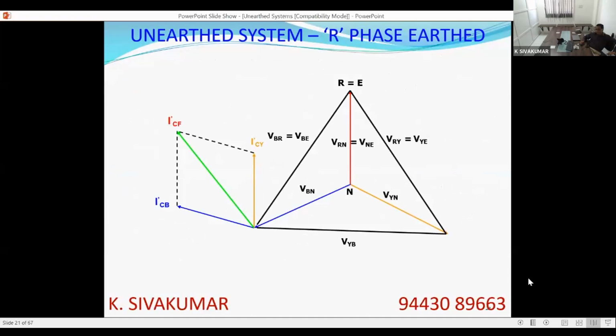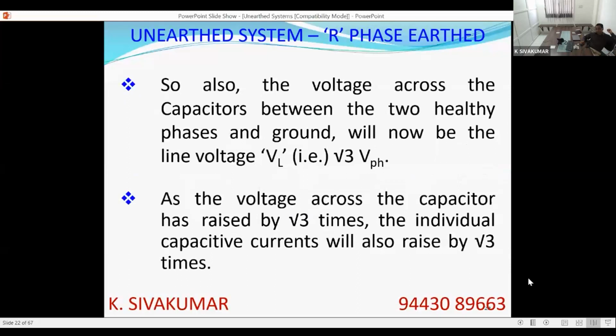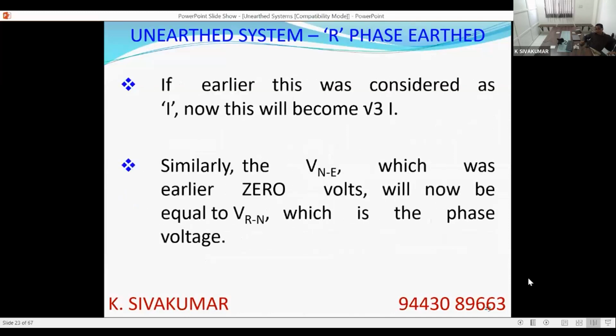That is, ICY will be leading VRY by 90 degrees, and ICB will be leading VBR by 90 degrees. The total net current flow during this fault, the capacitive discharge current, is the fault current. It is the vector sum of ICY and ICB. Since the voltage is increasing by √3 times, the current also will be increasing by √3 times. Earlier it was V phase by XC. Now it will be √3 V phase by XC. So the current will be no more I, it is √3 I now. Each of ICY and ICB will be √3 I now. So if you vectorially add √3 I and √3 I, it will become 3I.